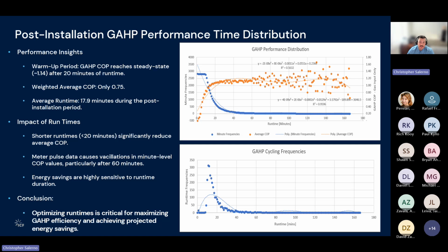And the reason why this wasn't running as long as it should have been is because of the undersized heat exchangers, and also the domestic hot water load going through the cold water wasn't enough to be able to meet the load of the gas-fired absorption heat pump. So it does not reach steady state COP. It kind of jumps around. And this is due really to the gas pulsing meters that we use for these. And so we really just need more data at this area and these longer runtimes, since we don't have much data. We need more data at these long runtimes to be able to average out and find more steady state performance.